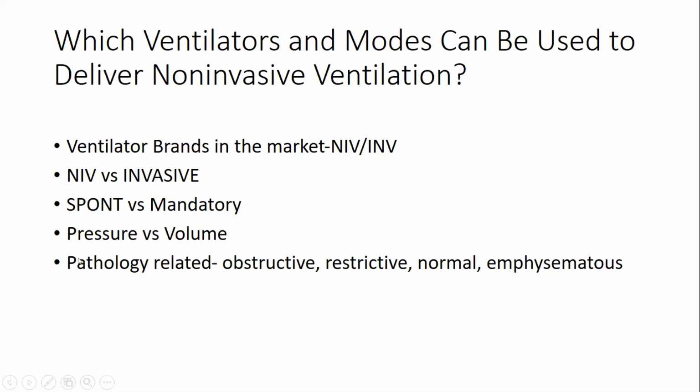Additionally, you have to think about what is the pathology of the patients, and some of the ventilators, especially the portable ones, are very specific to either obstructive, restrictive, normal or emphysematous pathological conditions. And each of these settings comes in with inbuilt settings that optimize the patient's ventilation.